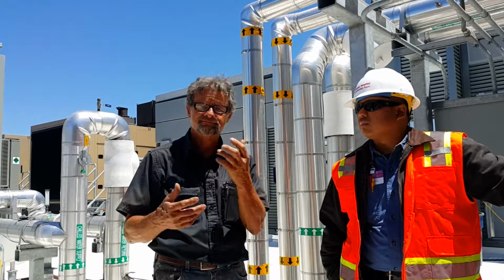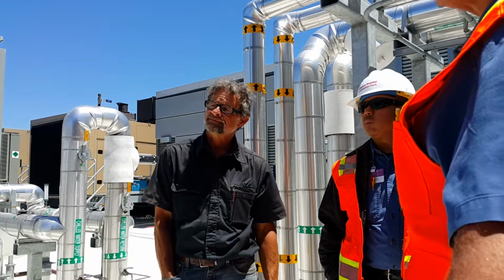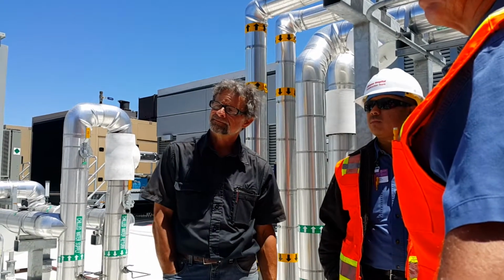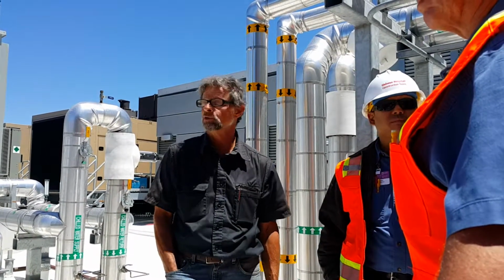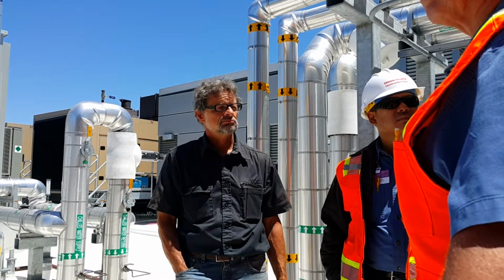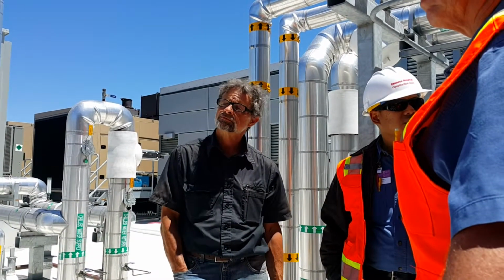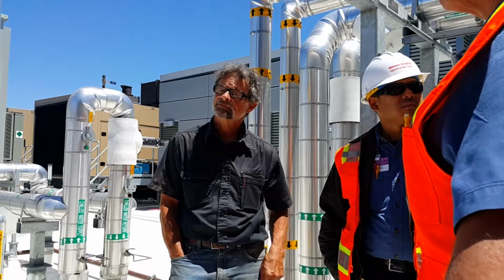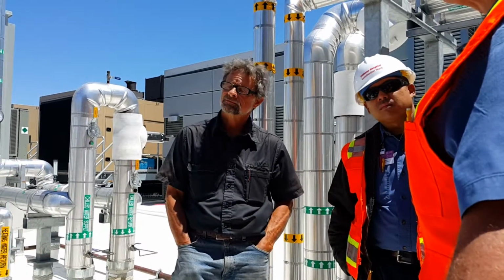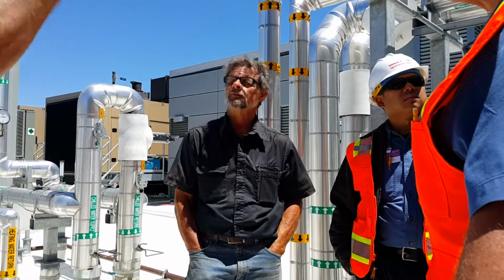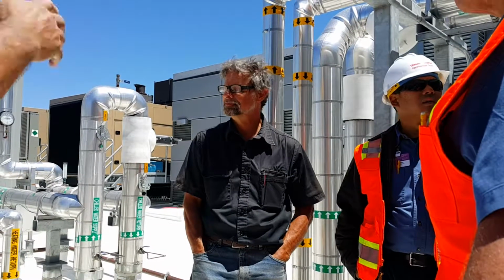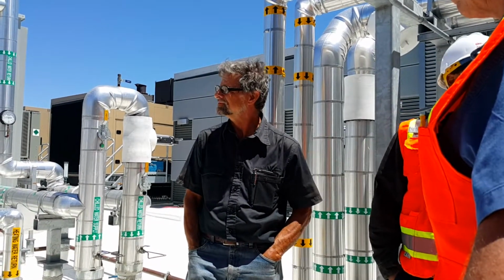Yeah, what they're going to do is if the ORs are down for a couple hours, it'll ramp down to 25% to save energy. So at night it'll ramp down, because we don't do 24/7 surgeries. We have to set up controls. When they go in and turn the lights on and touch the room, it'll start firing up. Ramp up. Yeah, go ahead and close that.